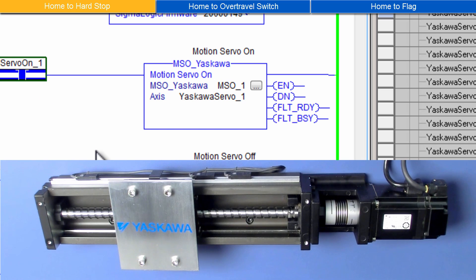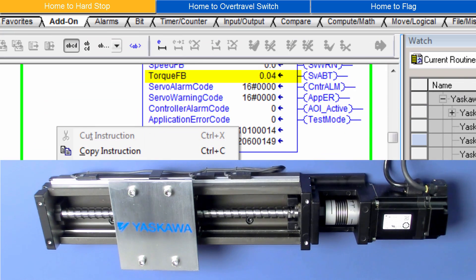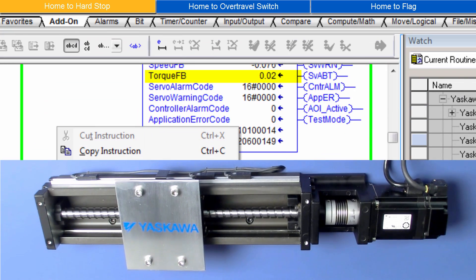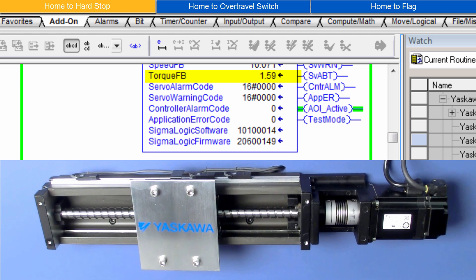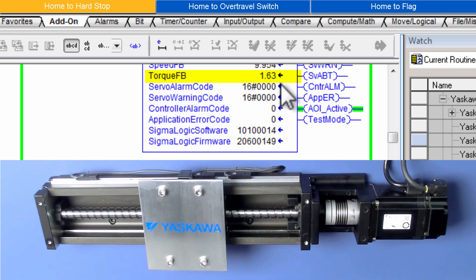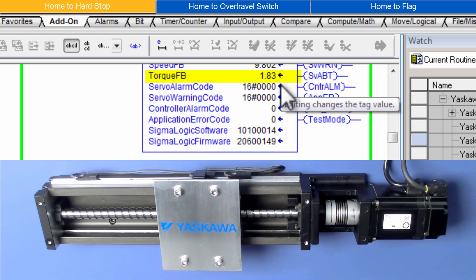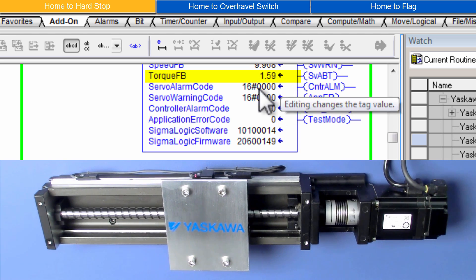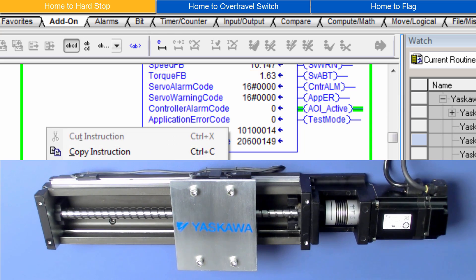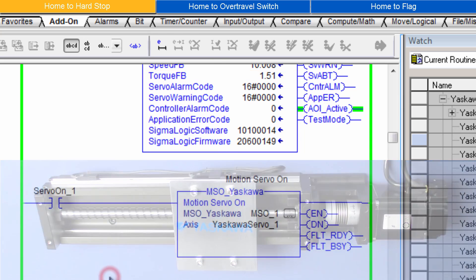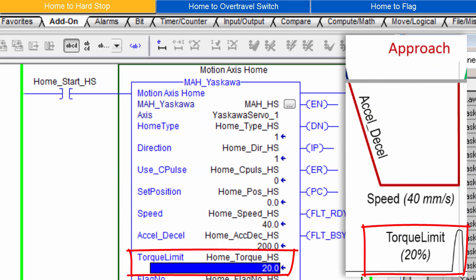For Torque Limit, estimate the torque with MCFG while jogging the motor. This axis is showing 3% out of 100% rated torque. And then set the torque limit somewhat higher. I'll try 20%.